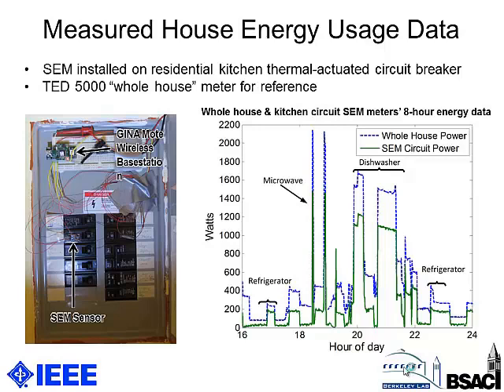While the SEM was installed, we plugged various known resistive loads into the kitchen circuit, right into the outlet, and monitored the change in output on our SEM sensor. That enabled us to connect the dots between the output of our sensor and real power in watts, and that result was then fed back into the software as the calibration factor I mentioned earlier.